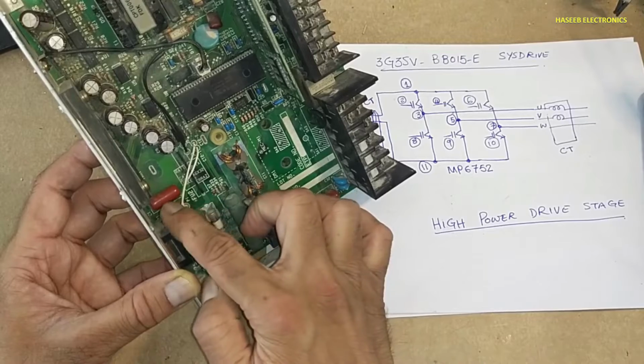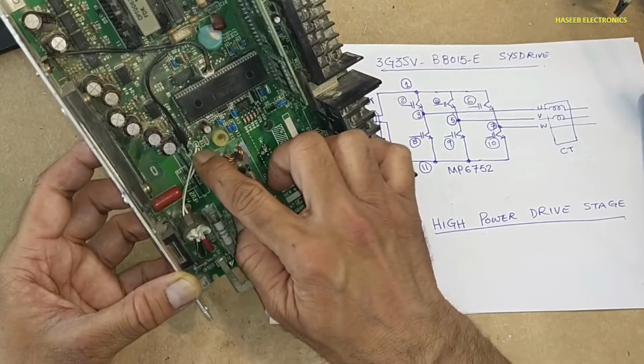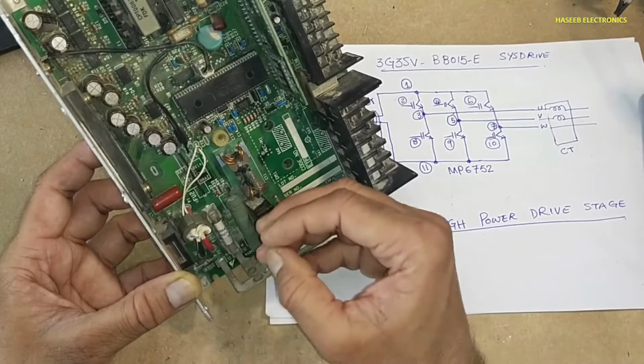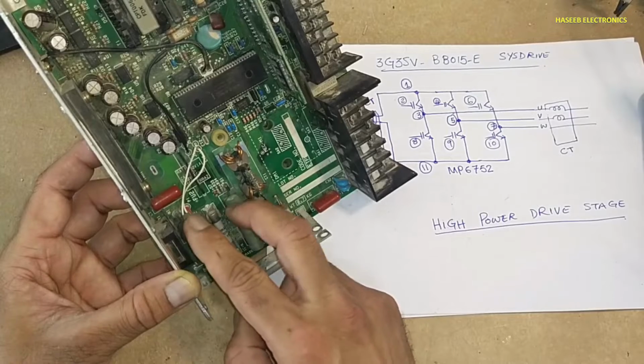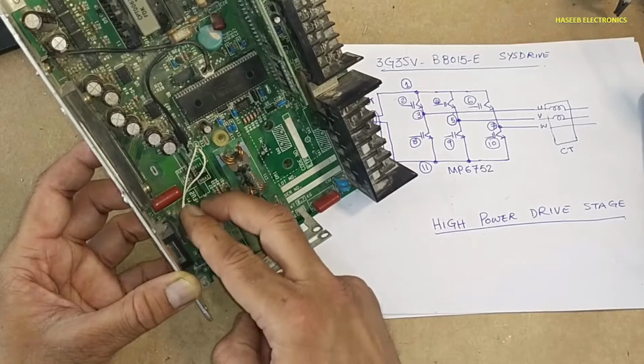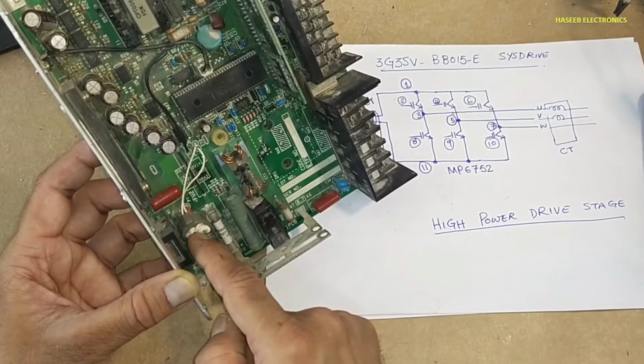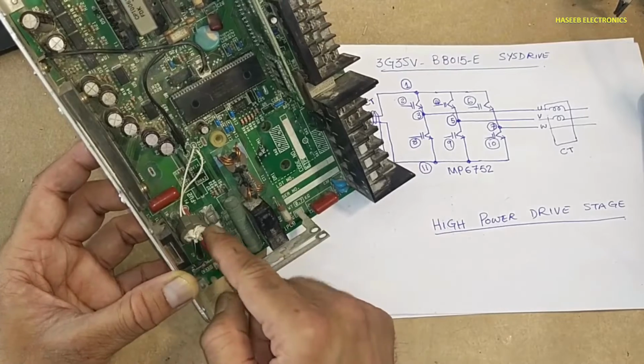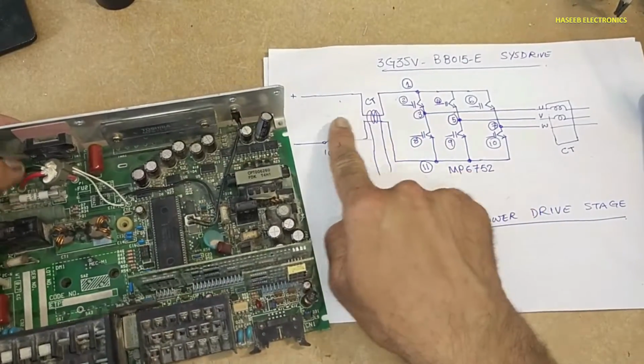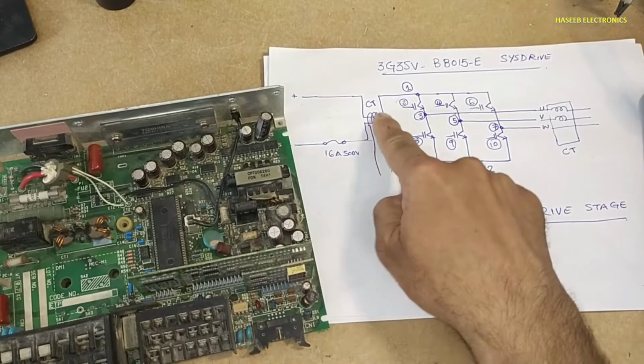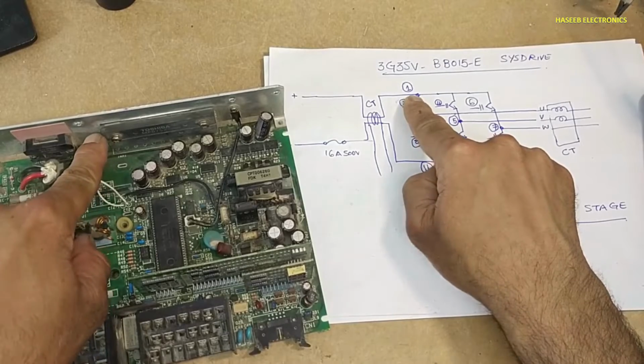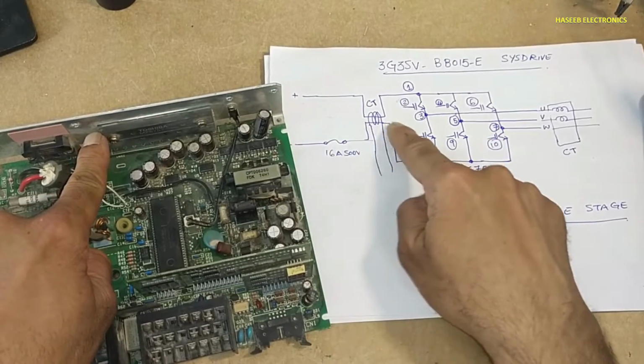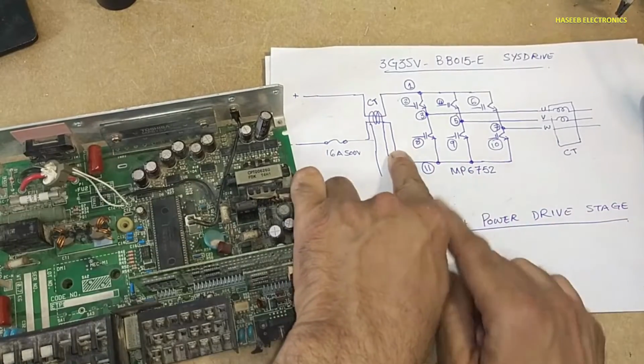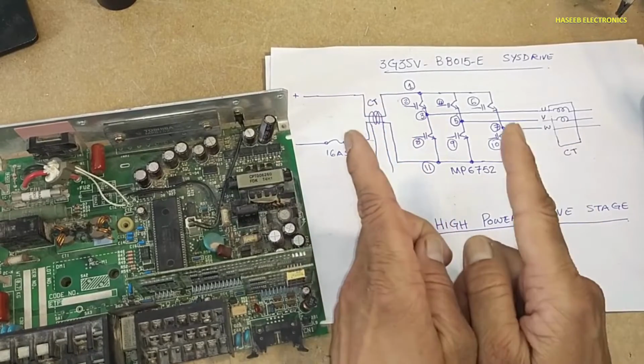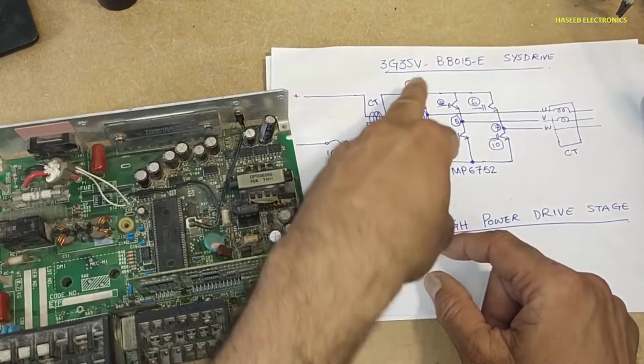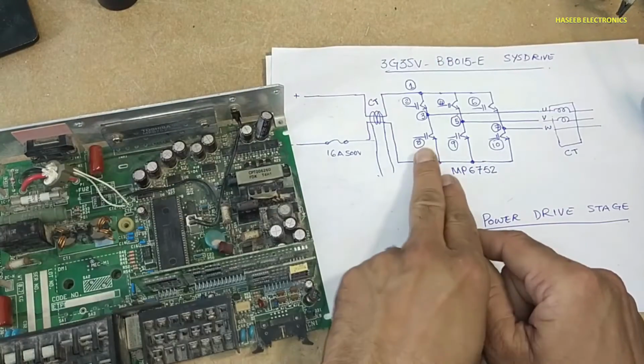On the ferrite core there is another winding that has two ends, this one and this one. It will tap voltage. The amount of current will produce a relative voltage on these two wires due to this current transformer action. We can say positive voltage is coming here and reaching pin number 1 of this IGBT power module. Negative voltage here.